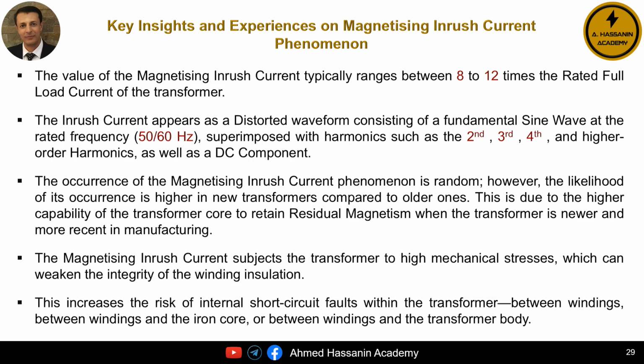The first point is that the value of the magnetizing inrush current is approximately 10 times, or roughly between 8 to 12 times, the rated full load current of the transformer. The second point, as we mentioned earlier, is that the magnetizing inrush current is a distorted waveform that contains various degrees of harmonics, such as the second harmonic and third harmonic, in addition to the DC component of the current.